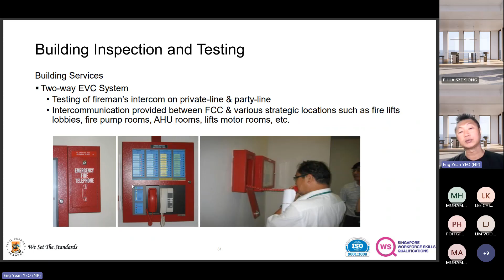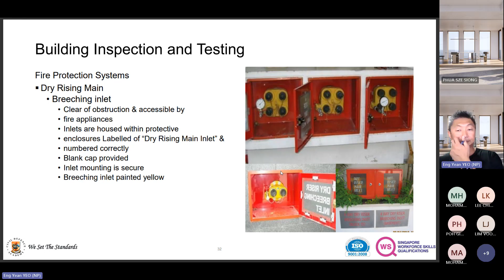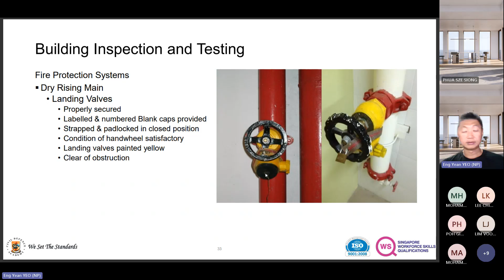Dry riser main level, main breaching inlet. Usually the blank cap is there and everything is empty. There is wording over here, so make sure it says the same thing. You must see the right thing, whether it is dry riser or wet riser. A dry riser is usually painted yellow, and you must put there dry riser main outlet. As mentioned, the numbering, let's say 3-5, 5-5, or 5-9, with a different wording sequence, will tell you a different thing. The blank cap must be provided and painted yellow. The landing valves for the dry riser will be padlocked and numbered, and they must be free of obstructions.